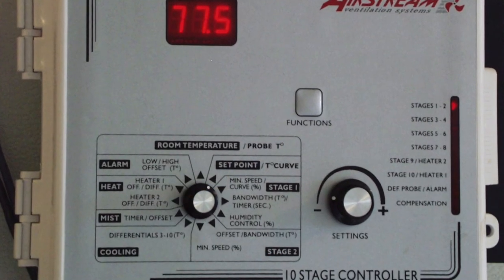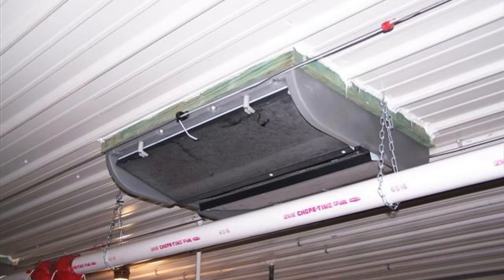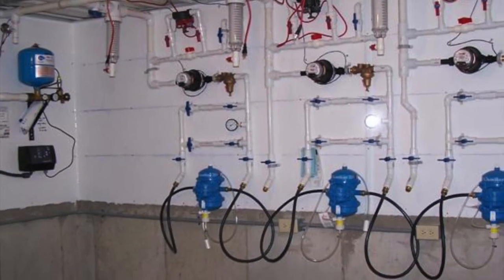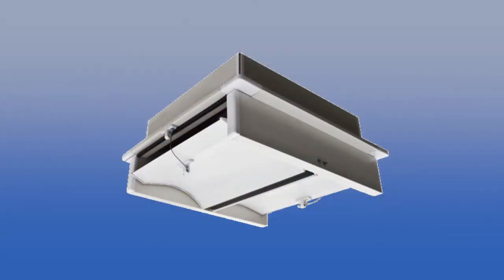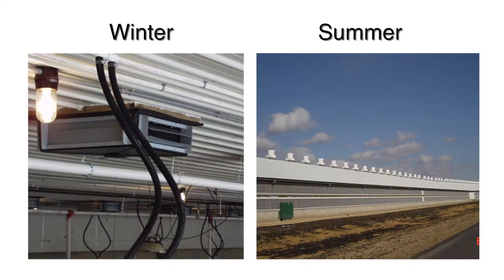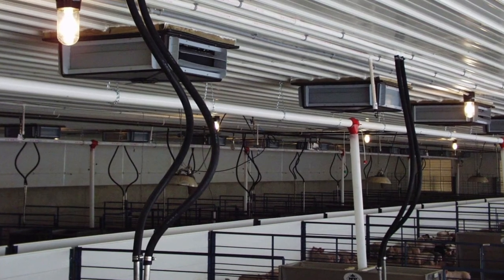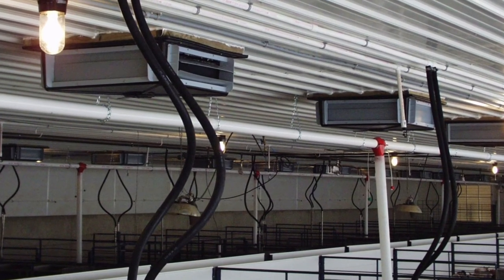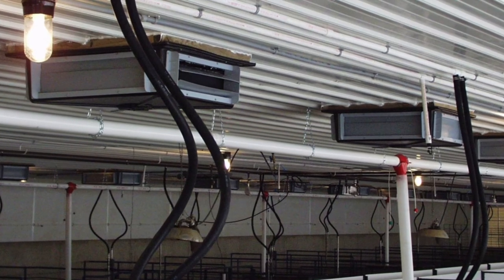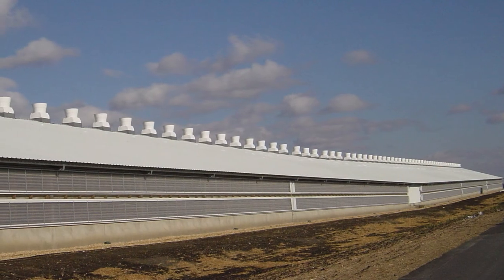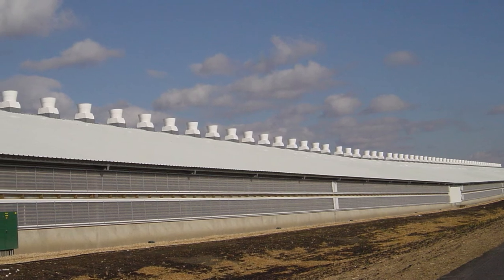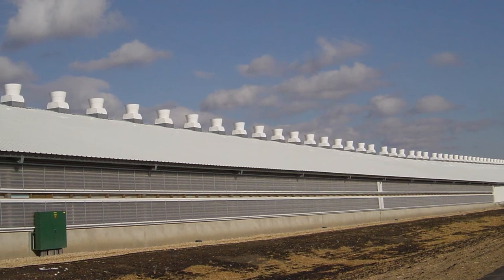The controller can also be programmed to open or close the inlets to maintain the proper static pressure in the building, to operate mixing fans, heaters, and sprinkling systems, or to manage a variety of other environmental control devices. The location of the inlets determines how fresh air is distributed inside the building. Often there are two inlet systems, one for the winter and one for the summer. The winter system, with low air flow rates, will typically have inlets in the ceiling or sidewall spread along the length of the building. The summer system, with high air flow rates, will usually have large inlet openings at the end of the building or in the sidewalls.